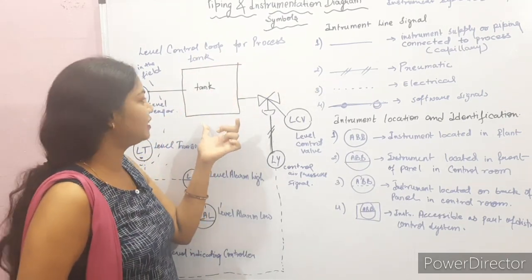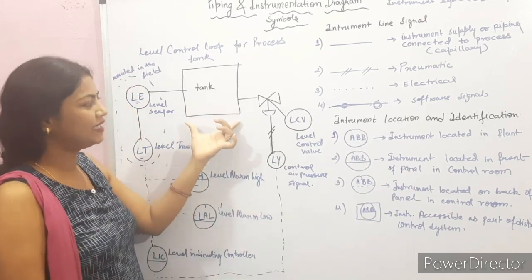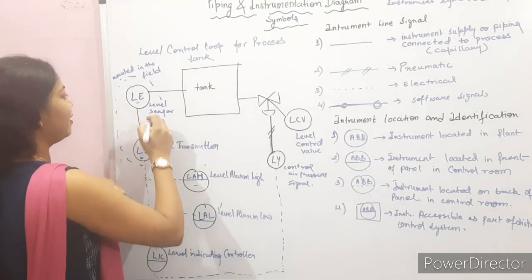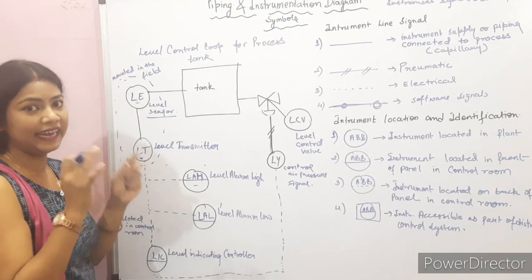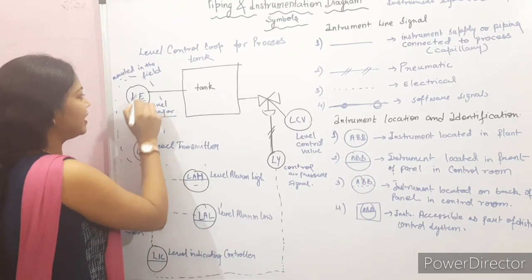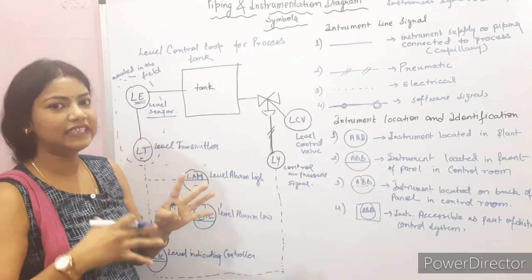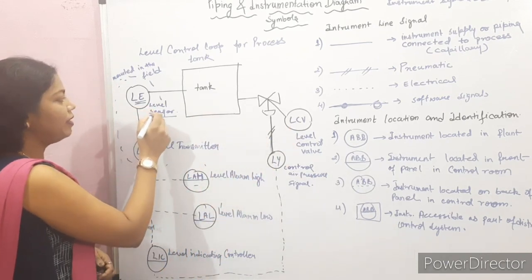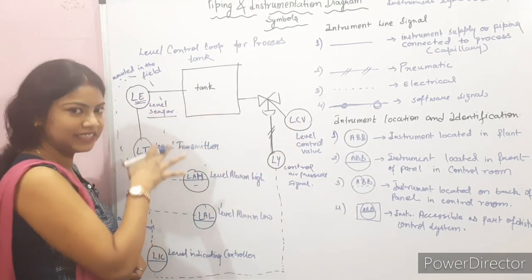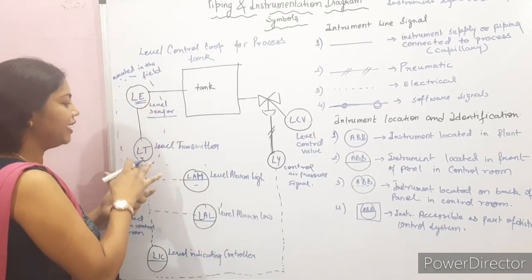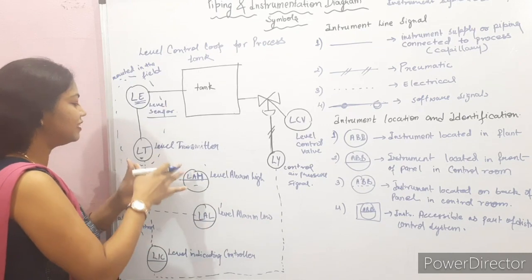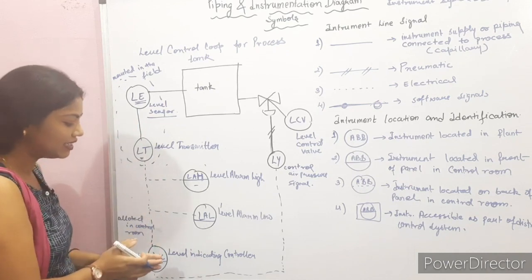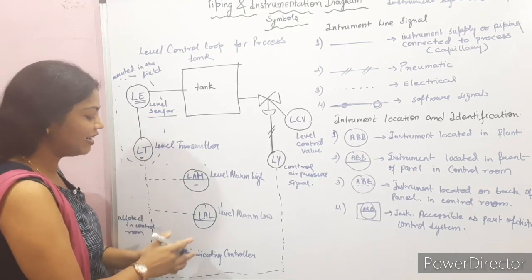We have a tank and we have to control or measure the level of this tank with the help of a sensor. Here we have the level sensor, represented as LE. The level sensor sends signals to the level transmitter. The level transmitter receives the signal, converts it to an electrical signal, and sends it to the level indicator controller.